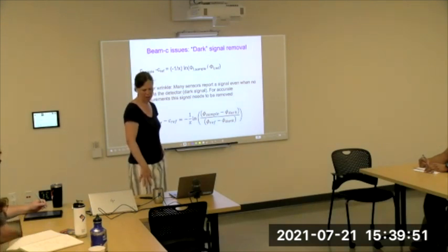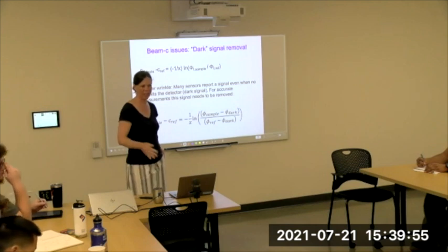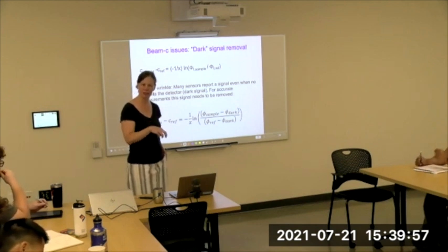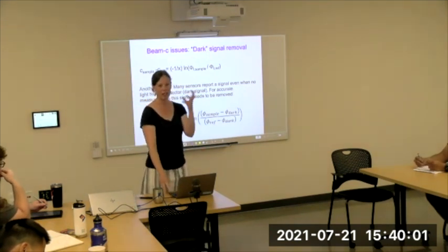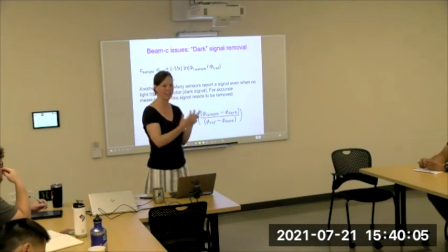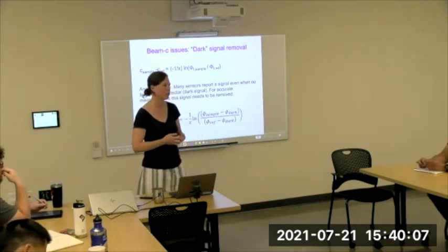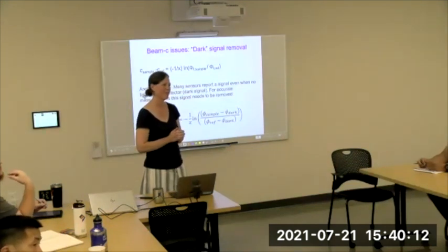For scattering sensors, the dark reading sometimes depends on what your power source is to your instrument. So you want to be careful that you're getting your dark reading with your sensor powered by the same thing that it's going to be powered by when you deploy it or use it for your sample collection. Sometimes it depends on if it's in fluid or not.